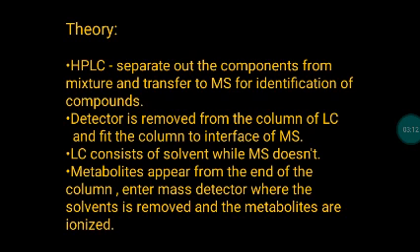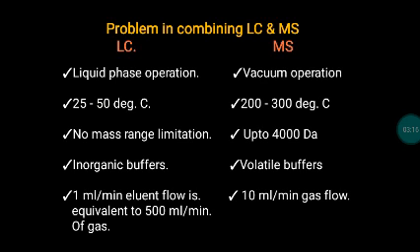Problems in combining LC and MS: these two are distinct instruments and their operations are also distinct. In LC, operation is in liquid phase; in MS, it is in vacuum. In LC, temperature is 25 to 50 degrees Celsius; in MS, it is 200 to 300 degrees Celsius. There is no mass range limitation in LC, but in MS, up to 4000 Daltons — heavy molecules cannot be ionized.